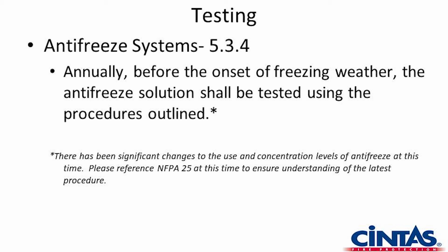Well, we started sprinkling houses about 15, 17 years ago or so. And in areas where it was subject to freeze, they would put antifreeze in them. But when the sprinkler heads would discharge because you had a small fire on your cooking appliance, the fire got bigger instead of putting the fire out. They realized that the use of the glycol and an improper mixed solution actually did more damage than good, because we made the fire larger than what it was to start with.